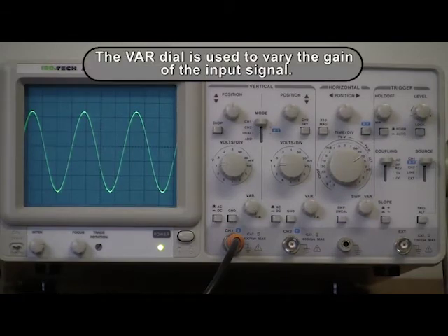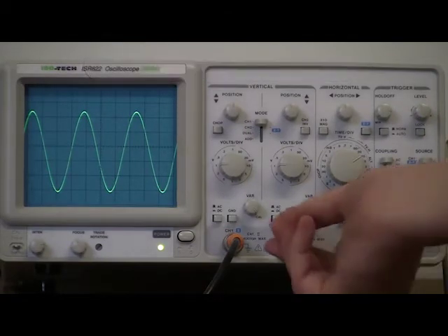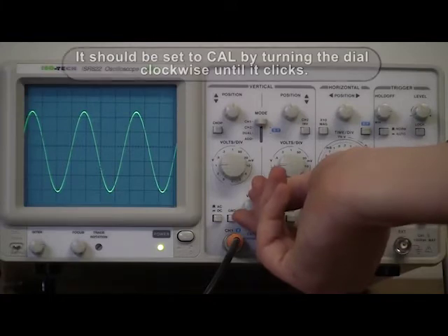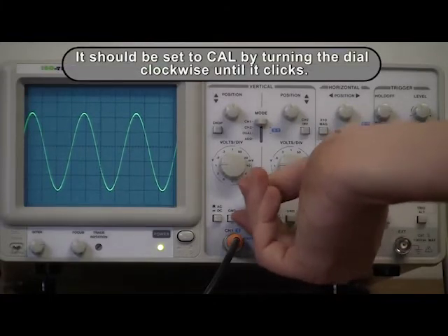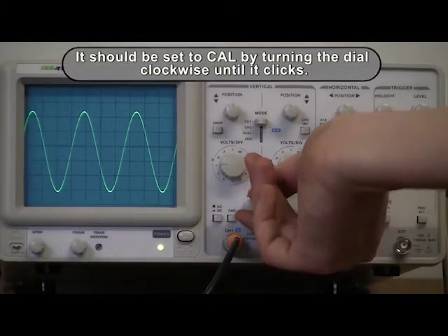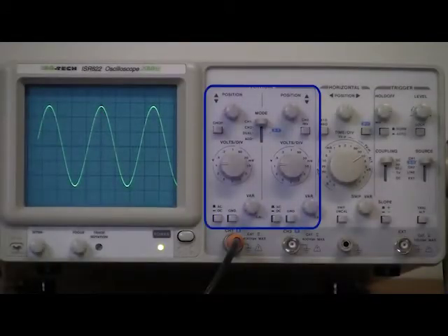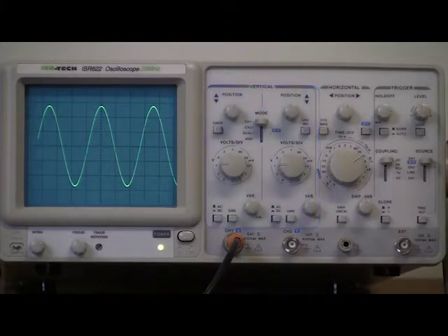The VAR dial is used to vary the gain of the input signal. It should be set to calibrated mode by turning the dial clockwise until the click is heard. The set of controls on the left of the oscilloscope vary the position and scaling of the vertical or voltage axis of the signal displayed on the oscilloscope screen.